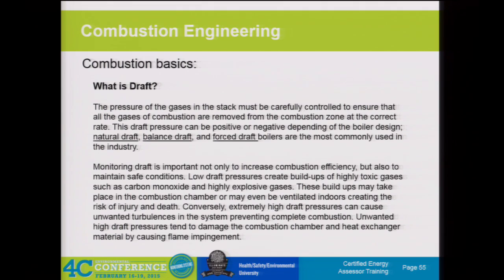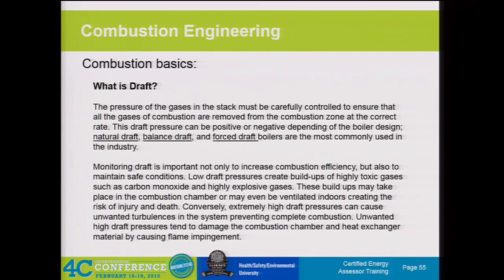So we're talking about our air-to-fuel ratio. The air systems of the boiler or process heater become very important—how we're maintaining that pressure and how we're supplying air into the unit becomes one of those critical points to understand for tuning the system. All of these units are set up, depending on the design, to supply combustion air. In some cases that combustion air is a natural draft, where we're just using the heat of the reaction to create a chimney effect and draw ambient air into the system for combustion. That works under certain situations, but there are not many boilers designed as a natural draft. Most boilers are forced draft or balanced draft type, using a fan to enhance the pressure and airflow to supply the oxygen for the reaction.